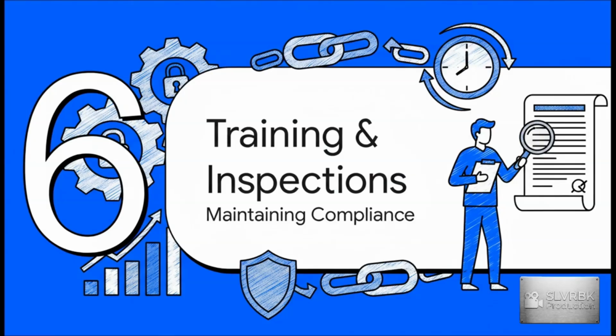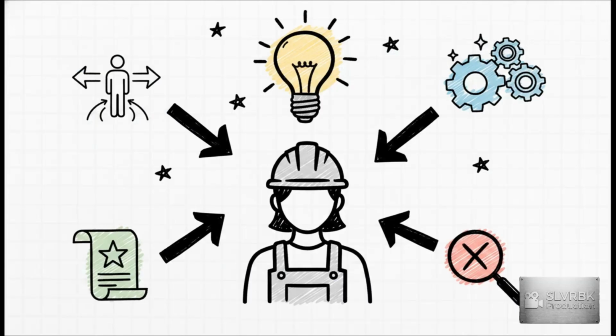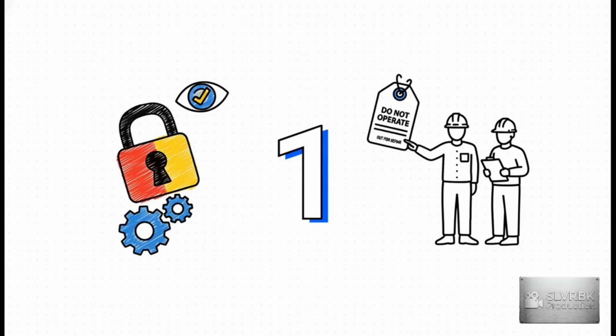Finally, Section 6, Training and Program Inspections. Having a great procedure on paper is totally useless if people forget it. Training is absolutely not a one-and-done event. Retraining is legally required whenever specific triggers hit, like changes in job assignments, new machinery or processes, new energy control procedures, or if you find shortcomings during periodic inspections. And speaking of inspections, OSHA requires at least one periodic inspection annually. But here's the catch. It must be performed by an authorized person who is actually not involved in the specific procedure being checked. This guarantees a completely objective review.